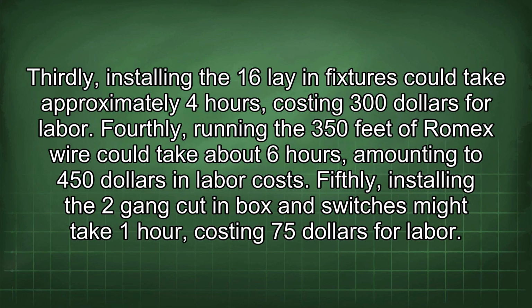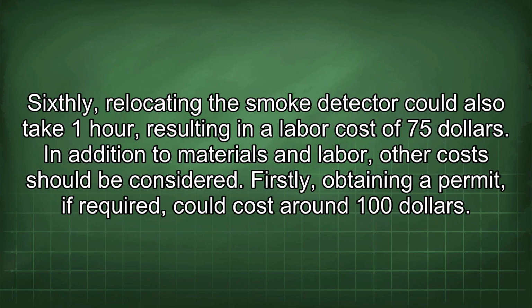Thirdly, installing the 16 lay-in fixtures could take approximately 4 hours, costing $300 for labor. Fourthly, running the 350 feet of Romex wire could take about 6 hours, amounting to $450 in labor costs. Fifthly, installing the 2-gang cut-in box and switches might take 1 hour, costing $75 for labor. Sixthly, relocating the smoke detector could also take 1 hour, resulting in a labor cost of $75.